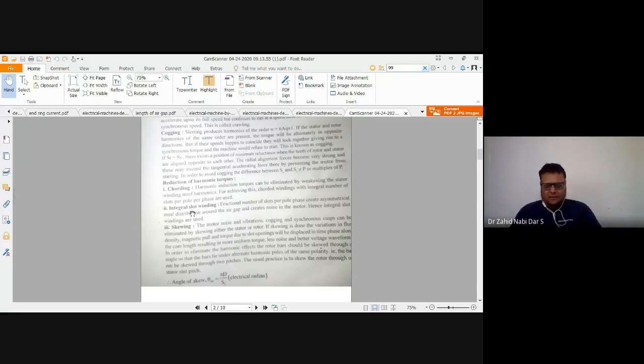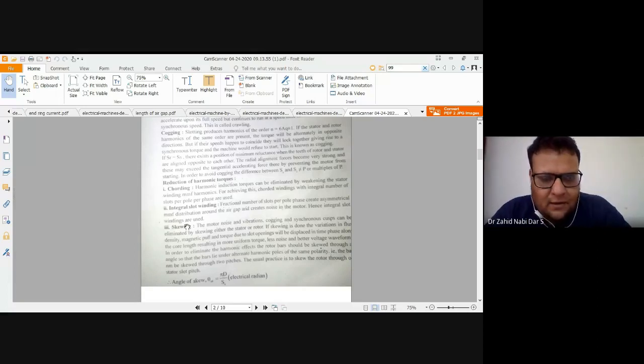Now you are going to the design class also. By now you must have understood what is chording. Cording is basically short pitching the winding. Now if you are having two windings and the pole separation is pi for 180 degrees, and you are not taking the exact angle of 180 degrees but less than 180 degrees, and the pole pitch you are taking is not exactly pi but a little lesser value, this phenomenon is called chording. Are you getting my point?